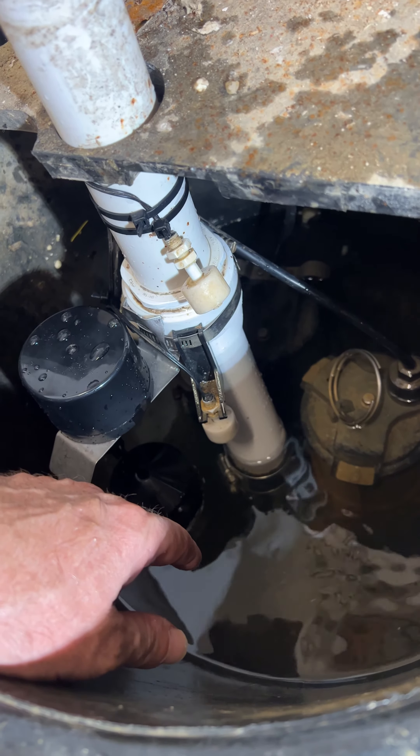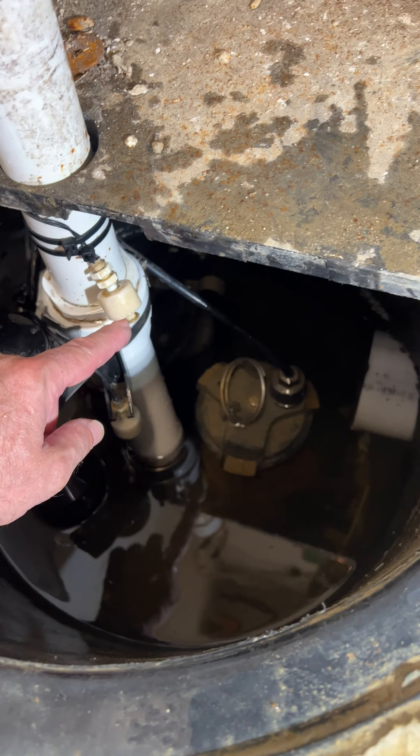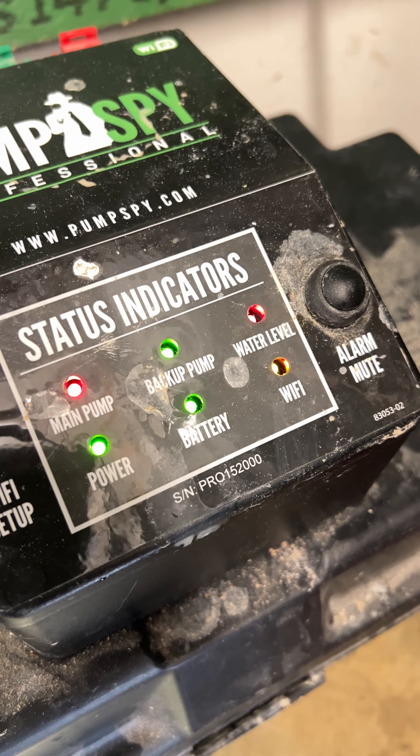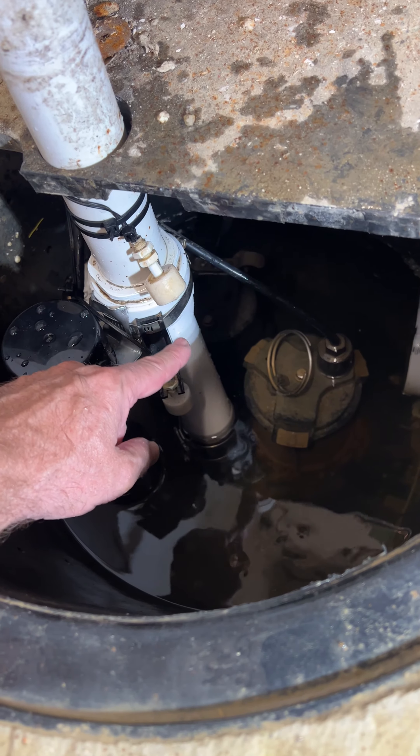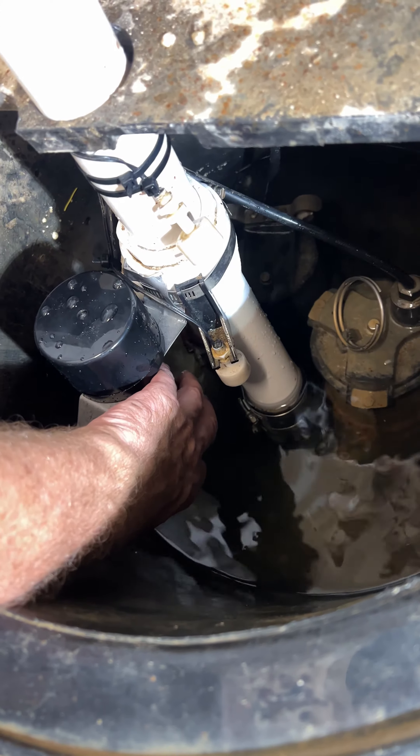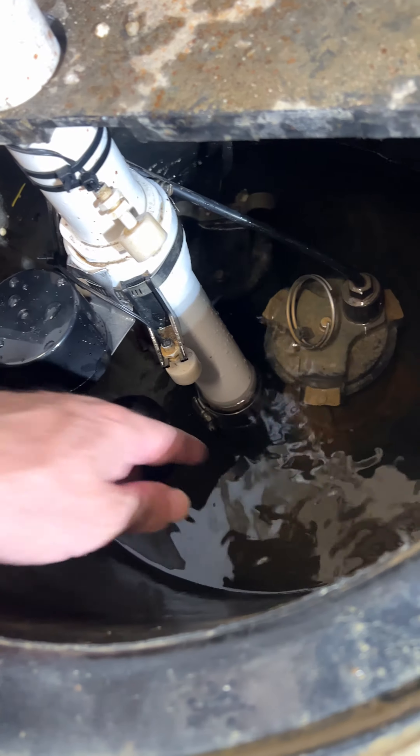So that's the test right there. This right here is a water level sensor. It will tell the system and let you know if the water level exceeds the backup pump and the main pump. It also triggers the alarm if the backup pump or the main pump is not running. To reset that, just activate the main pump and it will reset.